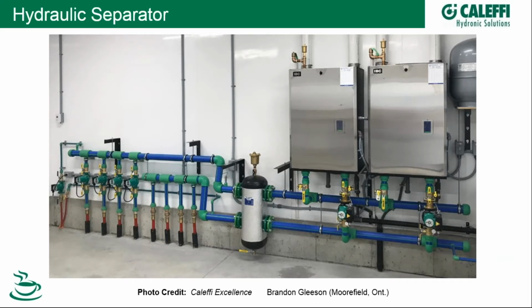Let's take a look at a photograph from an installation up in Ontario, submitted to Caleffi Excellence. Right in the middle, we see the Caleffi hydraulic separator, off to the right circulators, it looks like. So we have 5 zones. This is a radiantly heated chicken barn, if I remember right. This is going out to our radiant slab and then coming back, so this is the secondary side of our system. This is with 2 boilers connected in parallel to the supply header going into the top of the hydraulic separator and returning back here, all right? So these pumps don't know that one another exists, and they certainly don't know that these guys exist, by way of a hydraulic separator. We'll get into the inside of what these things look like in just a few slides.